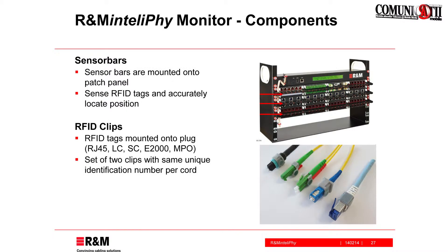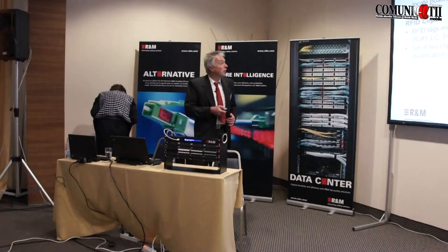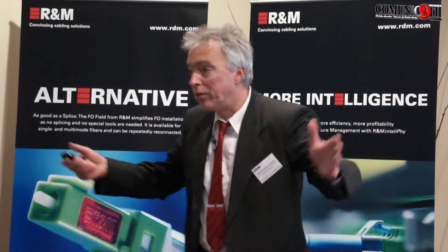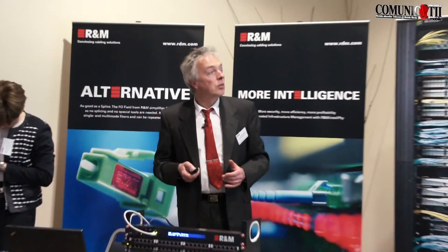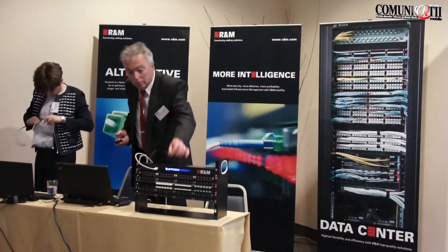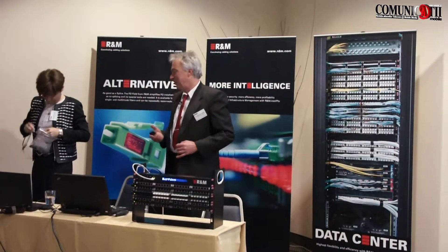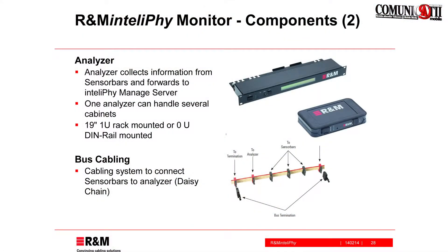The clips are read by the sensor bars. The sensor bars contain RFID readers, and with this we can detect the position and type of a cable in the network. Sensor bars and RFID clips don't work on their own — we have two additional components which we need. One is an analyzer (other people call this a scanner in the AIM world). Then we have a cabling system — a small ribbon cable running from the analyzer to all sensor bars. Using this cable, the analyzer can read what is written on the RFID tags.